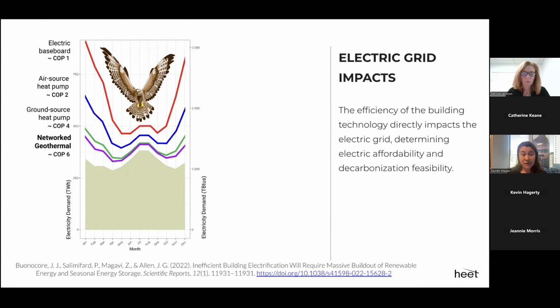With the red, of course, no one's going out intending to put in electric baseboards to electrify - that would be nuts, we all agree I'm sure. That winter peak would be near impossible to meet. Also, most heat pumps deployed on an individual building basis have an electric resistance backup. What does this mean? Unfortunately, it means that if that is how we have deployed, and we hit a crazy winter peak and all of those electric resistance backups come on, we need that grid - that red line - which is a problem.